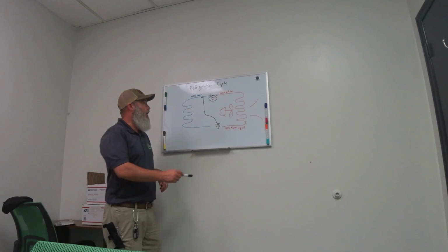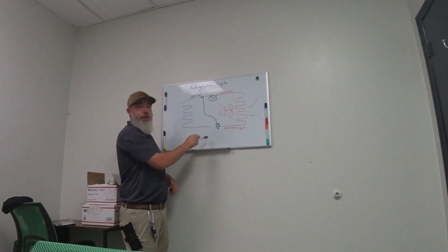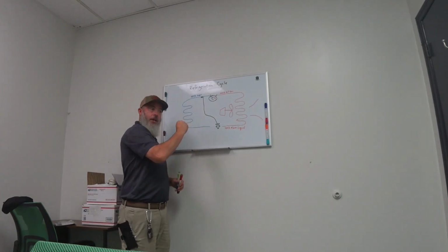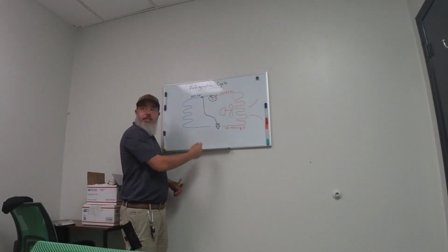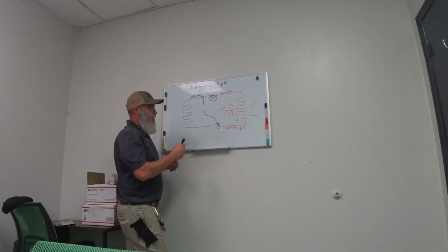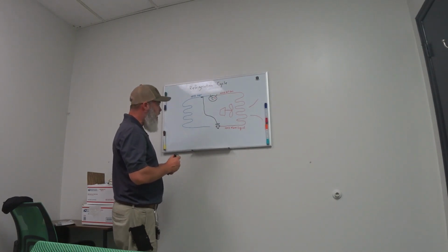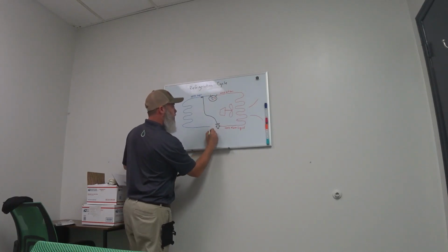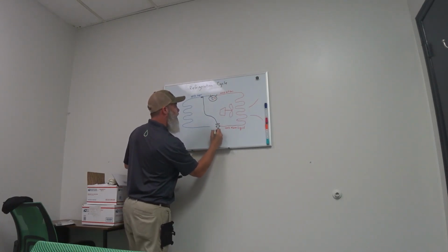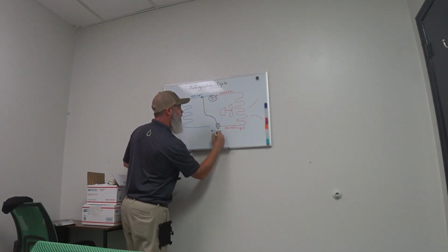It's got a refrigerant charge in it, and this is just a capillary that goes to this power head right here. It meters up and down, up and down. It's got a little needle inside of it that meters that refrigerant as much as it needs to. So you've got 100% warm liquid coming in here, and when it first comes out, right here, it is about 80% liquid and about 20% vapor.